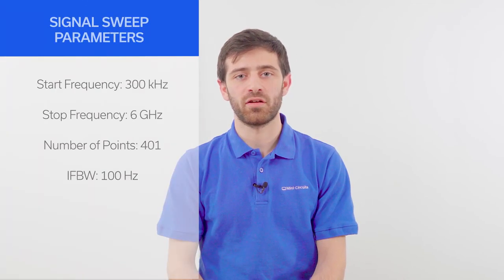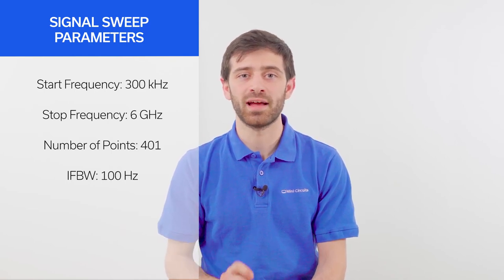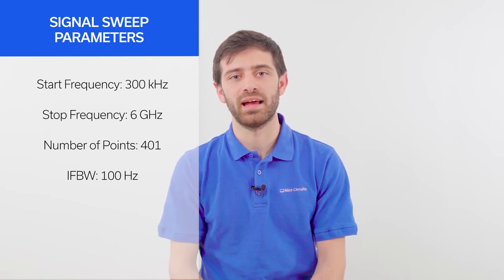Start the calibration process by setting the signal sweep parameters based on the device you're measuring. It helps to have the device connected while you're setting the start frequency, stop frequency, number of points, and resolution bandwidth so that you get an idea of what your measurement will look like after calibration. As a rule of thumb, recalibration is typically required any time these settings are changed.